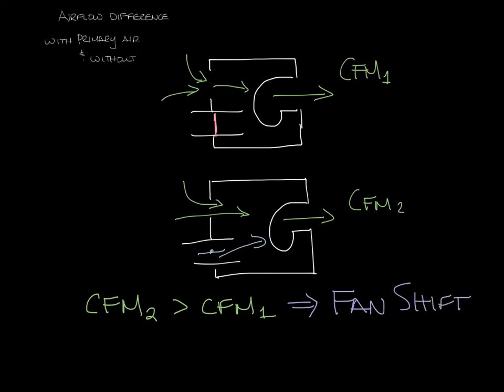As a box manufacturer we take all this into account when we work on our designs and this was more of an issue with PSC motors. Now that a lot of people are switching to ECM motors which can compensate for changes in pressure and adjust the airflow accordingly.